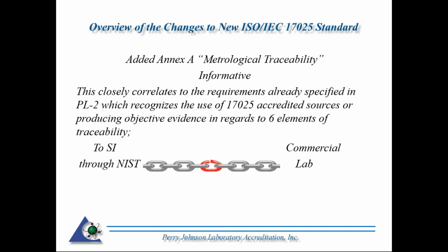Hence, if you're using a facility who's accredited to do the calibration and is under an accrediting body under the ILAC MRA, I always say that's a slam dunk. That's considered an accredited calibration. You cannot be accredited but can still produce accredited results. The lab needs to, and this is specified in the annex, present the elements of traceability in order to consider them as being traceable.